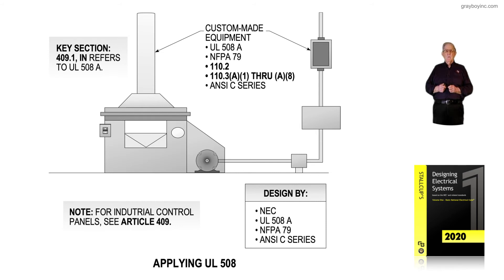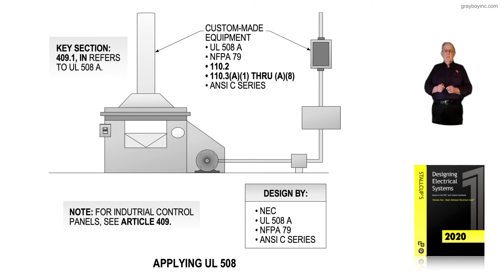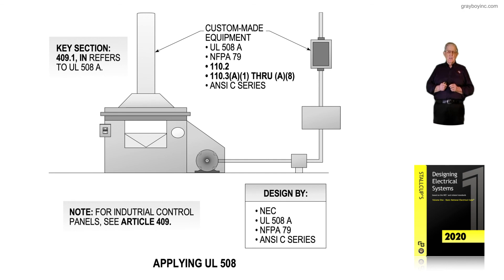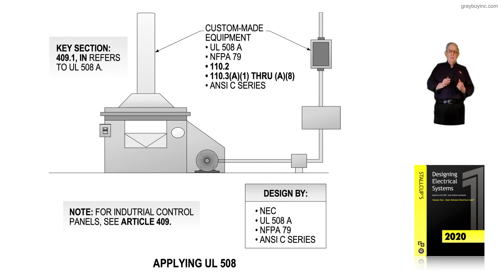We would design by the NEC and UL 508 or 508A, whichever contains the rules. If that industrial control panel is in conjunction with the operation of industrial equipment, we'd also look at NFPA 79. The ANSI C series would be used only if needed. Figure 1-26 deals with applying the UL 508 standard in relation to what that industrial control panel is designed to operate and control.